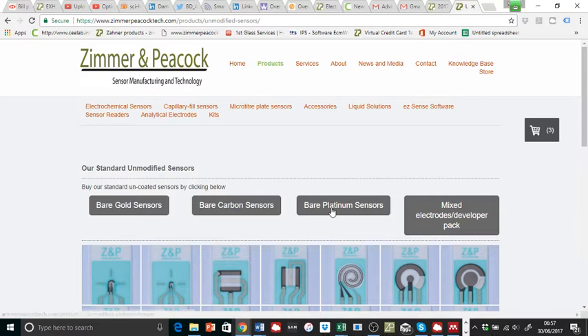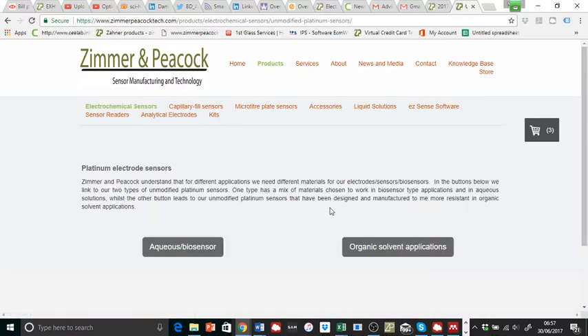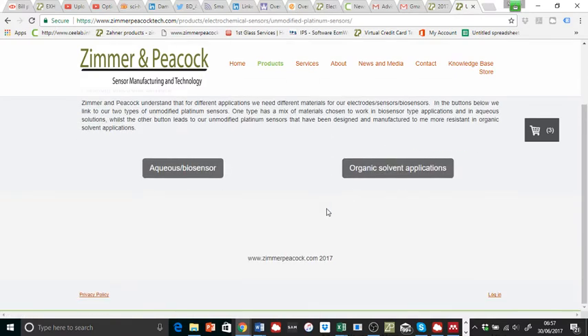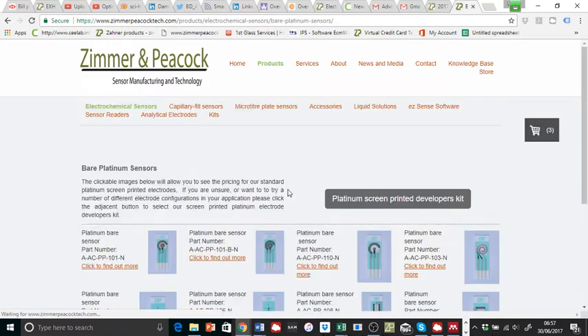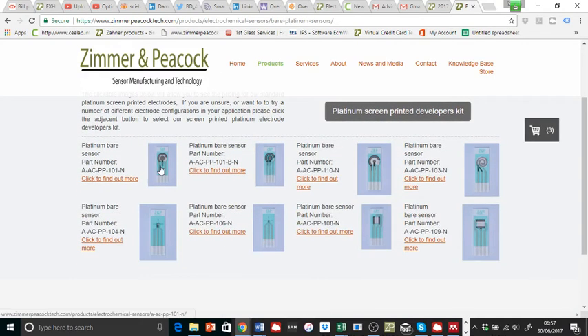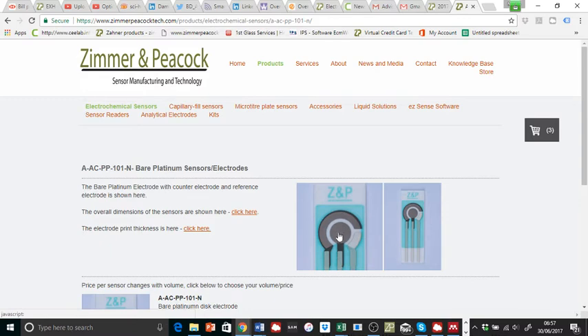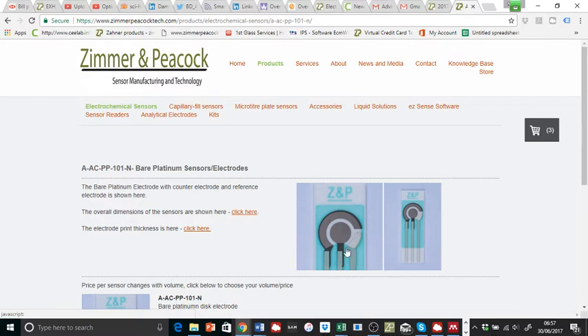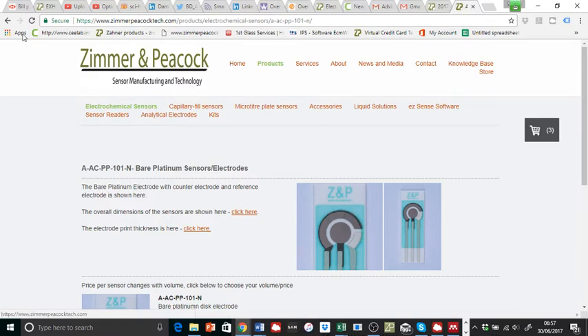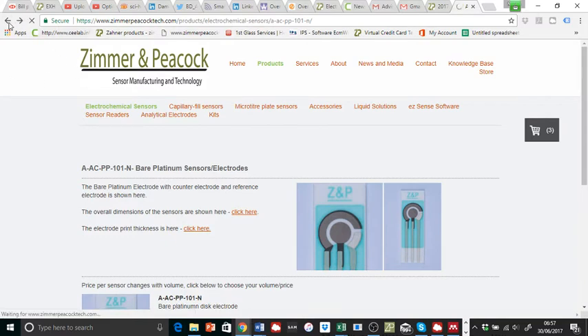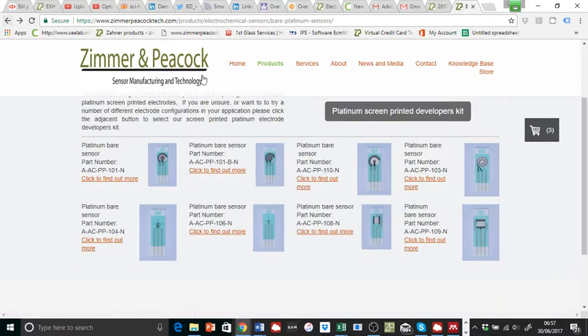Let's look at the bare platinums that we have. Because in bare platinum we have two types. We have a type like this where we have a platinum working electrode, a platinum counter electrode, and a silver-silver chloride reference electrode with a blue dielectric or a light blue dielectric. In this case we could do a darker blue dielectric as well. On the face of it, quite close to the specification that the customer asked for.